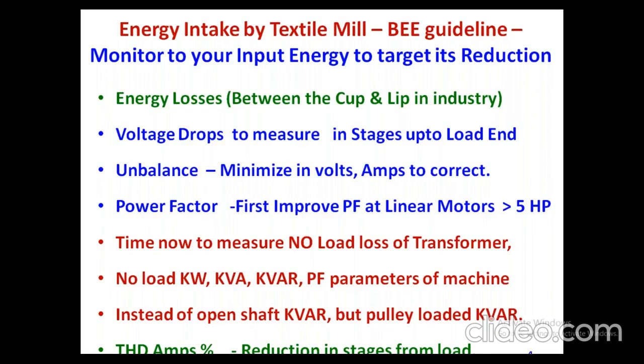So always, instead of an open shaft kVAR for the given capacitor sizing, we can take a pulley loaded kVAR. These are the practical deviations we make so that we give enough kVAR for the motor at the motor end. The THD amps, the H5 and H7 that arise due to this VFD, need to be reduced, and the reduction has to be done in stages from the load itself. Normally we say the harmonics have to be house arrested. If that is done from each and every load end, the harmonic impact on the given textile mill will definitely be very much less, both on the current side and ultimately on the voltage side as well.